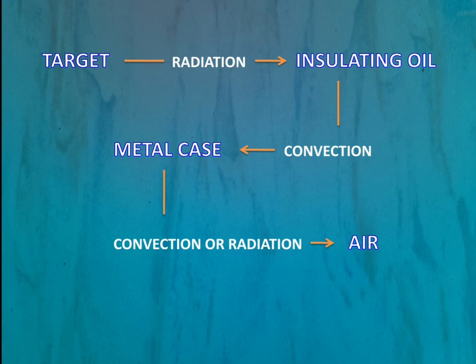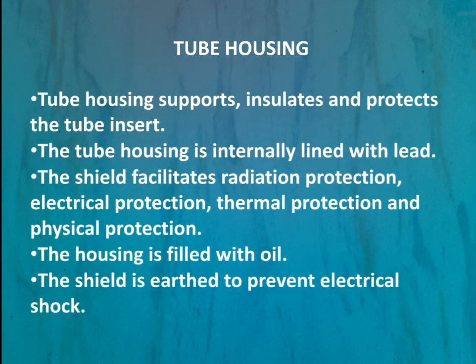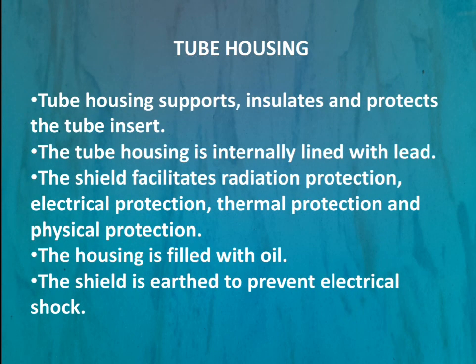This is how the excess heat generated at the target area is transferred to the external environment, facilitating proper working of the x-ray tube. Moving on to tube housing: the entire x-ray tube is placed inside a lead case, and that lead case forms the tube housing. The tube housing provides support, insulation, and protects the glass envelope. It is internally lined with lead, which is why it is called a lead case.